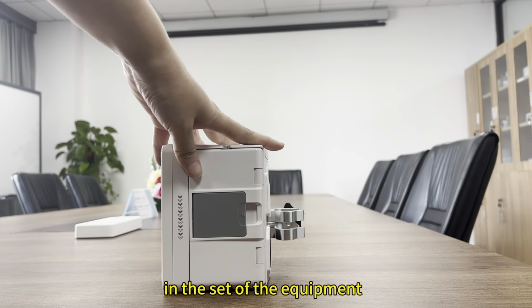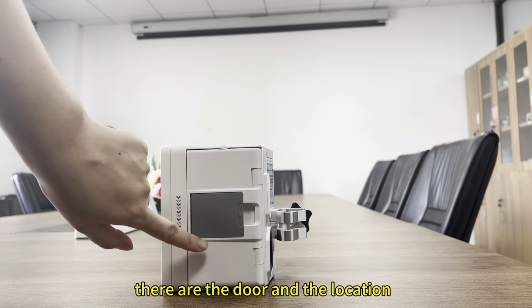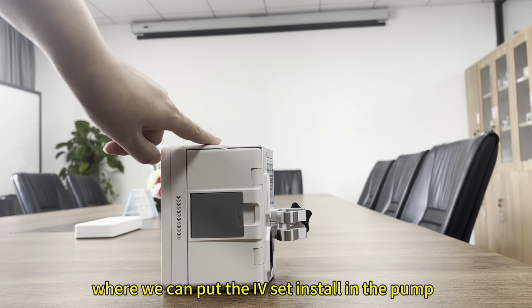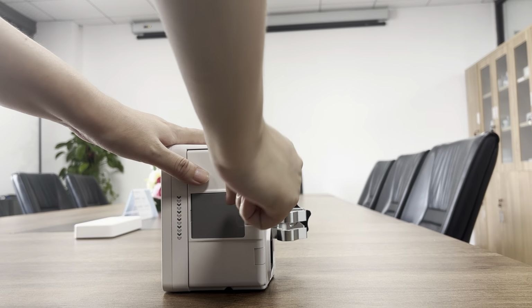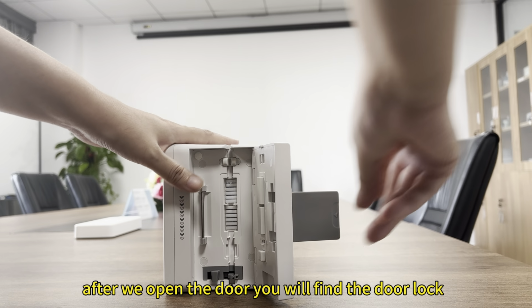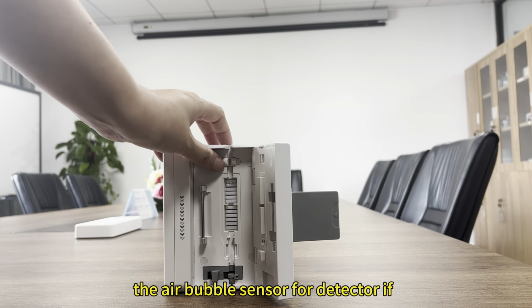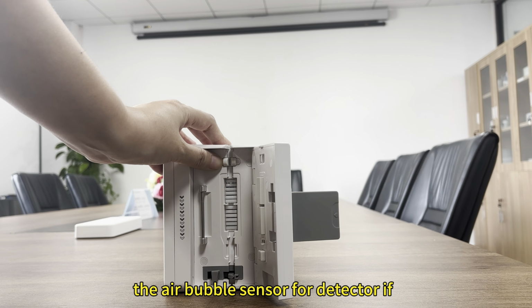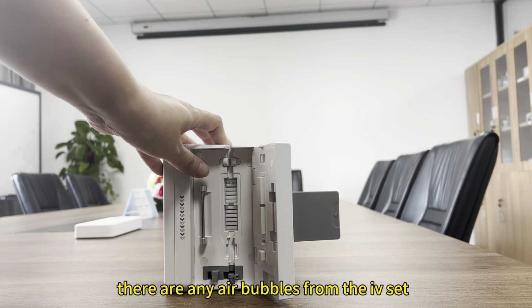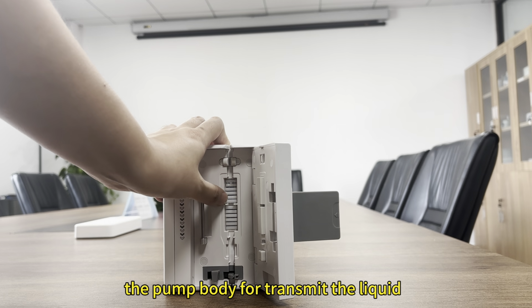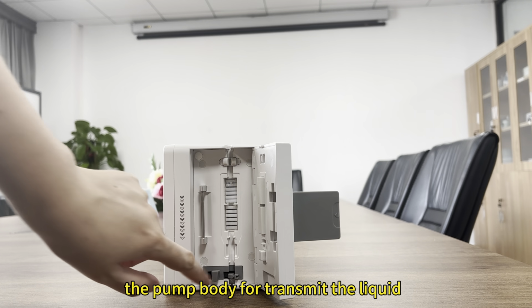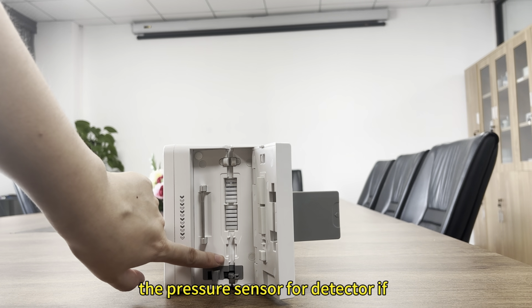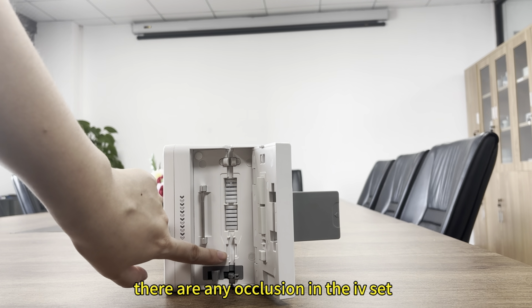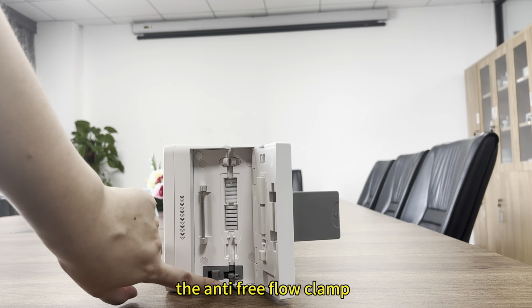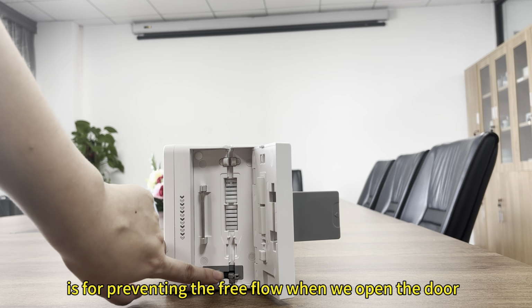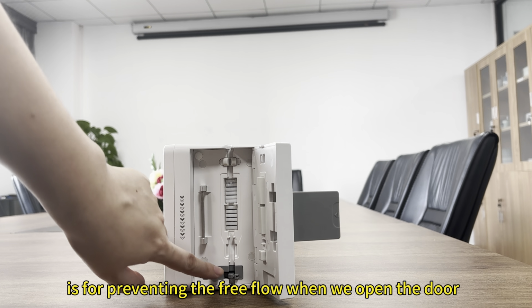On the side of the equipment, there is the door and the location where we can put the IV set installed in the pump. After we open the door, you will find the door lock, the air bubble sensor to detect if there are any air bubbles from the IV set, the pump body to transmit the liquid, the pressure sensor to detect if there is any occlusion in the IV set, and the anti-free flow clamp. This clamp is for preventing free flow when we open the door.